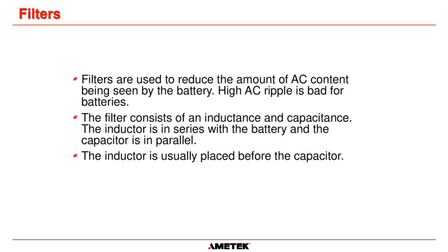Filters are used to reduce the amount of AC content being seen by the battery. High AC ripple is bad for batteries, especially valve regulated batteries, because it causes internal heating of the cell. The filter consists of an inductance and a capacitance - the inductor is in series with the battery, and the capacitor is always in parallel. The inductor is usually placed before the capacitor, and capacitors are just like a small short-term battery. They have electrolyte inside them, and that does degrade with time and temperature. Most capacitor manufacturers recommend that DC electrolytic capacitors are replaced at least every 10 years, if not sooner. If the ambient temperature is hot, just like for batteries, that time period is reduced.